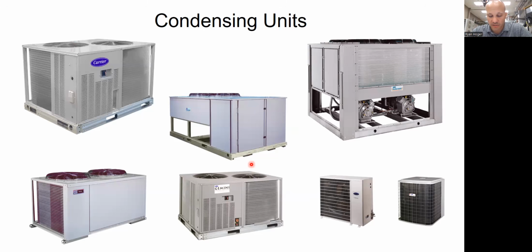Where will you see a condenser? The most common application would be like a supermarket. If you go in a supermarket, there's usually in the back room a mezzanine with tons of compressors there. And those compressors are all piped to all the freezers and refrigerated cases. And then the condenser is out on the roof. For some reason, that industry has evolved that the compressors are in a mezzanine and the condensers are up on the roof. I don't know why it evolved that way. It just did. Maybe there's a technical reason. I don't do supermarket work, so I don't know. But that would be an example of it.